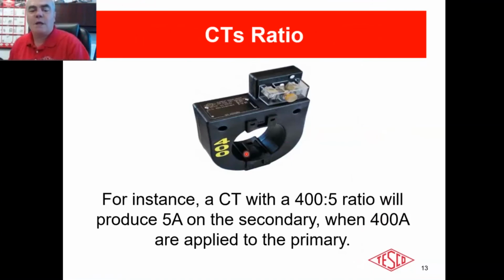Somebody asked a question. What type of current transformers are best to use? Donut or bar types? There is no better or worse. I personally like the bar types better. The donut types are a little easier to install, I believe. But actually the wires going through your donut transformers, as you get to the larger and larger ratios, like a 2,000, 4,000, 5,000, 8,000 to 5, the way that the service goes through that donut is important to the accuracy of that transformer.